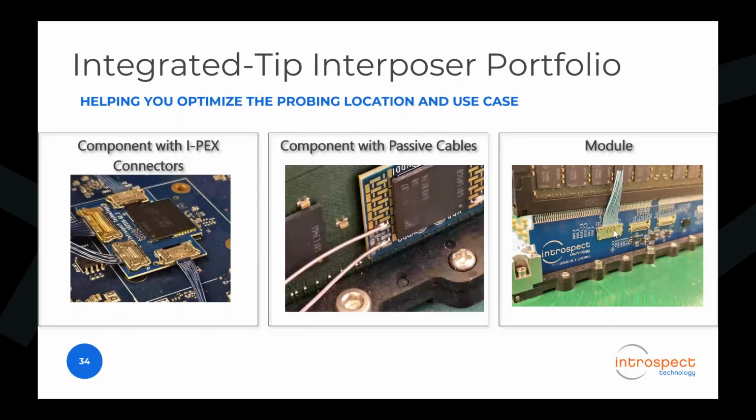What is the difference between RSH3 and RSH2? It's a bandwidth. So RSH3 is our latest active probe solution. It's not on the website yet, but it's shipping as of this month, and that has an analog bandwidth of up to 35 gigahertz. So this is really getting into the territory of the most expensive scope probes that you'll find on the market right now.